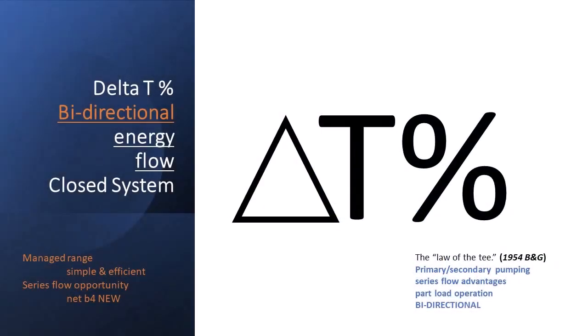They were looking at how hot the water needs to start before, if we bleed a little onto this unit and a little onto that one, it'll still be okay by the end. We can set up the system so it won't change more than 10 degrees from one end to the other, even if everybody's on.